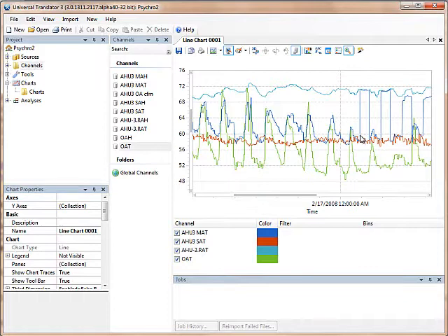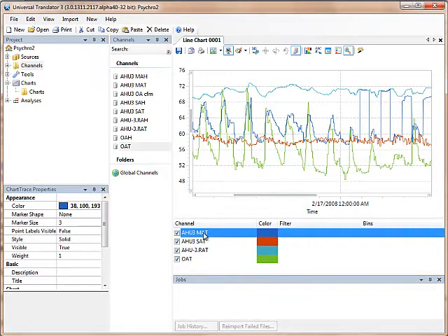So the mixed air temperature, which is dark blue right there, suddenly jumps up all the way to return air temperature. So somebody made a change to the control logic of this air handler, and now the air economizer is no longer active, and I want to get some kind of quantification of how much money that costs. And the best way to do that is to figure out the tonnage of cooling that the air handler is providing.